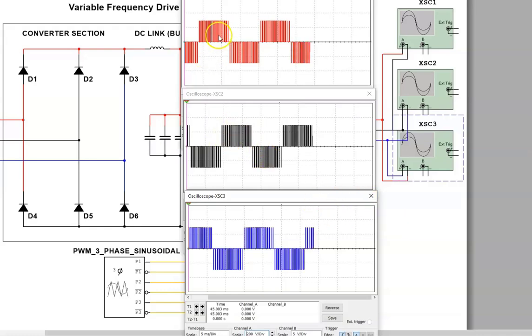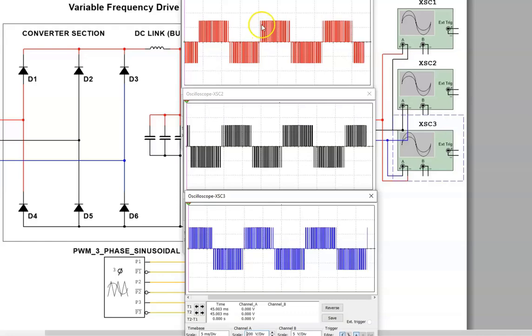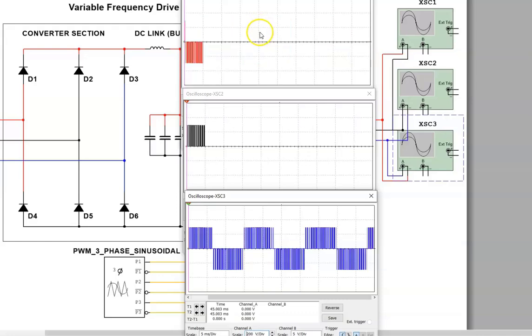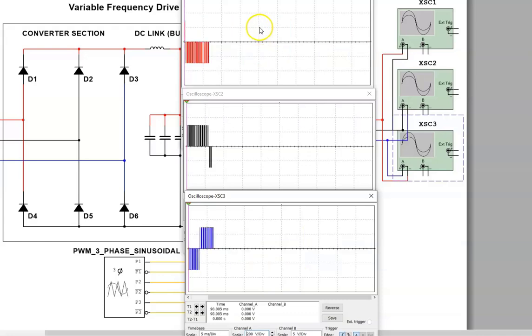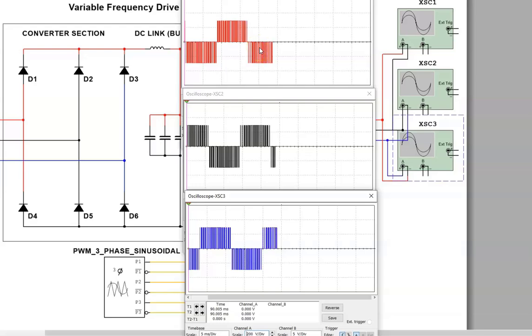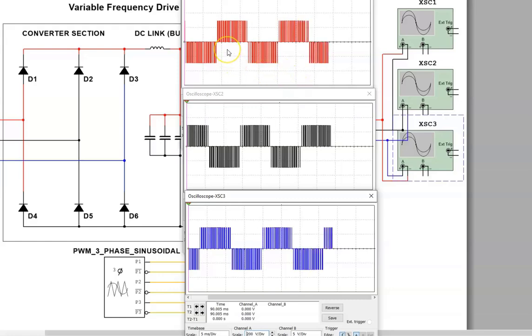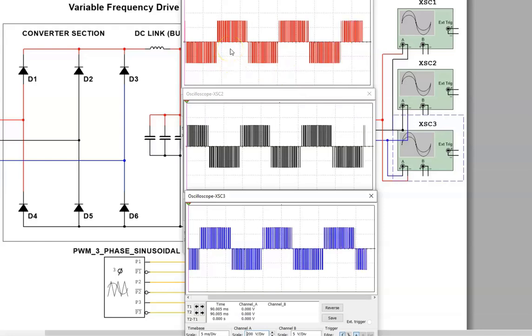Now, you'll notice that they don't line up. They're out of phase with each other. So the starting point of each square vertical waveform pulse are out of phase by 120 degrees each. And that's why I couldn't put it all on one screen because you would see so much overlap, you wouldn't be able to see each waveform. So each motor lead sees these pulse width modulated output waveforms.